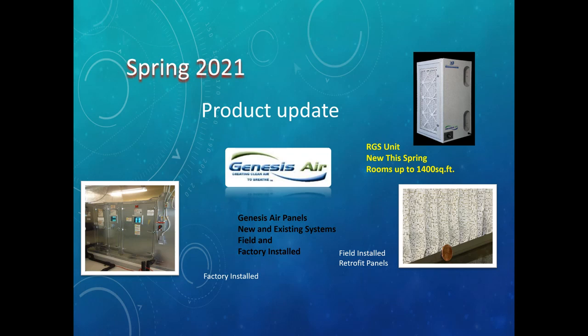You can field install the panels. One nice thing is they take very little space—side load in a Trane unit only takes 6 inches, front load in an air handler only takes 13 inches. Static pressure drop is 0.05 at 500 feet per minute, with minimal energy use. We're really looking forward to the in-room unit.